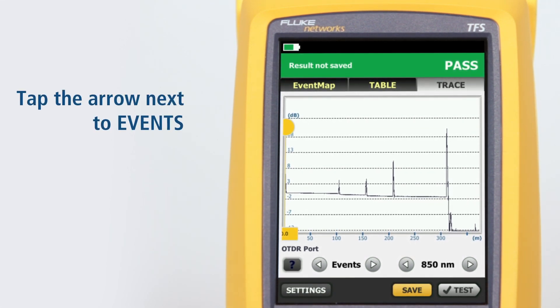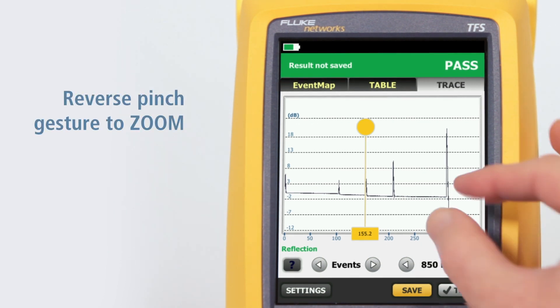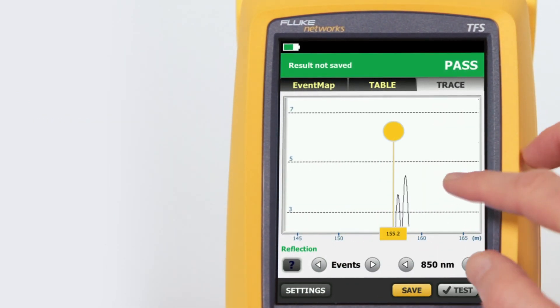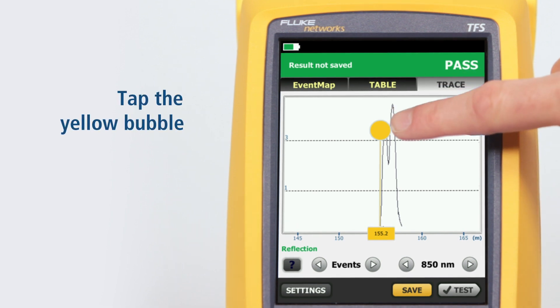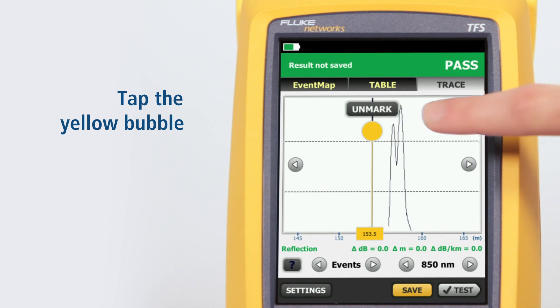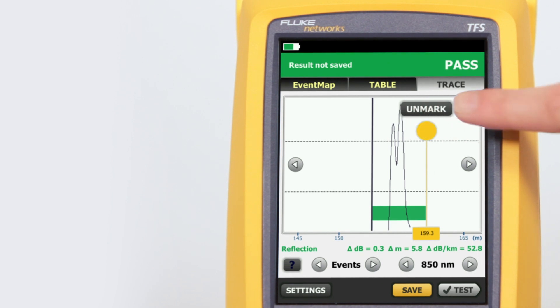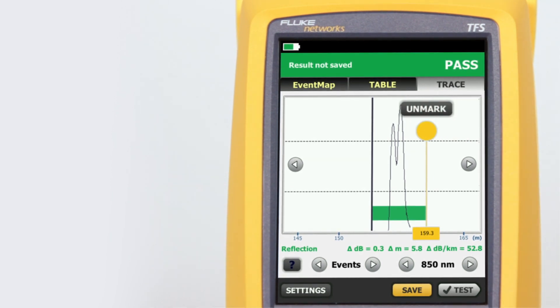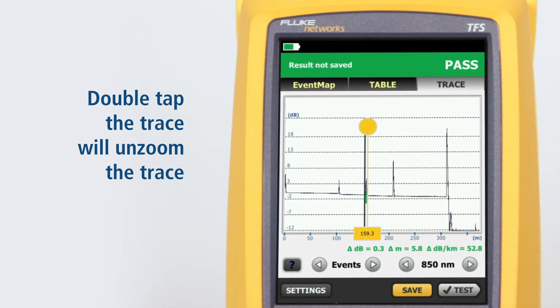Tapping the arrow next to Events will move the cursor to the next event on the trace. Using a reverse pinch gesture will zoom the trace at the location centered between the two fingers. Dragging a finger across the screen moves the trace in the direction of the drag so that events of interest may be centered. Tapping the yellow bubble on the cursor activates the fine positioning arrows and the Mark button. The cursor may be moved by dragging it to the desired location. The Mark button sets the marker, and dragging the cursor allows manual measurements to be made with the cursor readout at the bottom of the trace. Double tapping the trace will unzoom the trace.